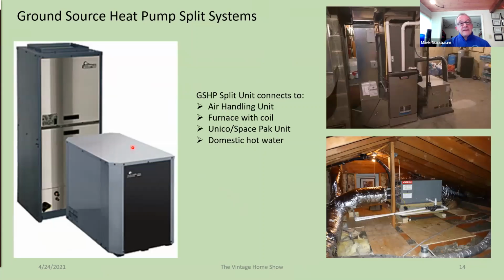The split system, this box here is the box that is connected to the ground loop. Usually it sits in your basement. I use a refrigerant line set just like I would on a traditional air conditioning set to connect this box to another box inside. That could be an air handler unit like this. It can be a furnace, a coil on top of a furnace setup like this. It can be a fan coil unit. It could be a Spacepak unit or a Unico unit, high velocity system unit. Those work as well. Again, these have the ability to create domestic hot water.